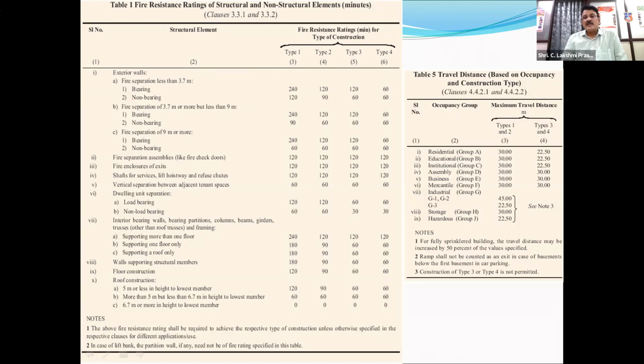So all the exits should have minimum 2 hour fire resistance, because exits include a door, a corridor, a staircase, a ramp. All this requires minimum 2 hour fire resistance, and we should not use any combustible material in construction of these exits. And there are other floor construction, wall supporting structural members. So various time prescriptions. Fire resistance should prevent the fire from affecting the structure for that prescribed time.